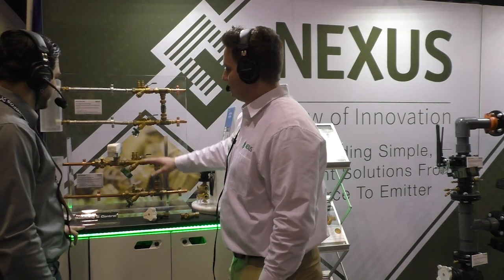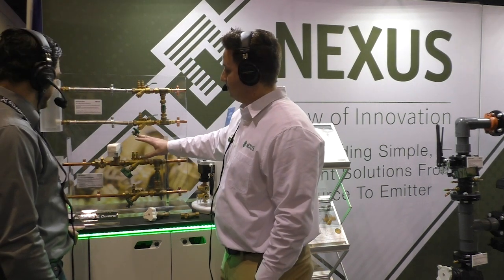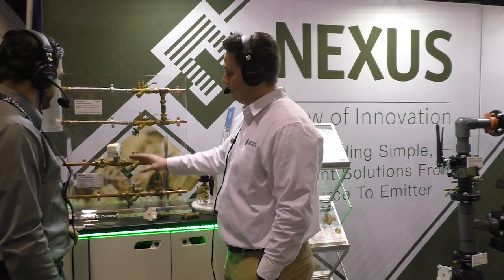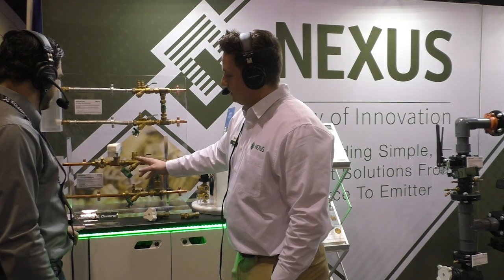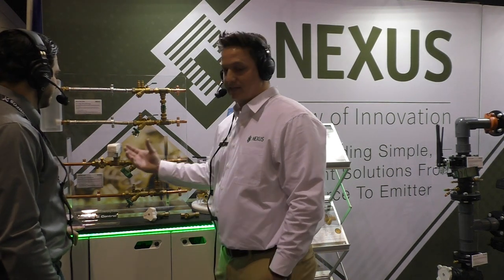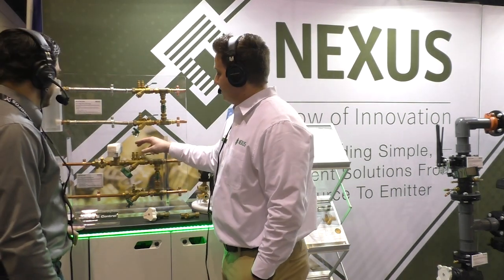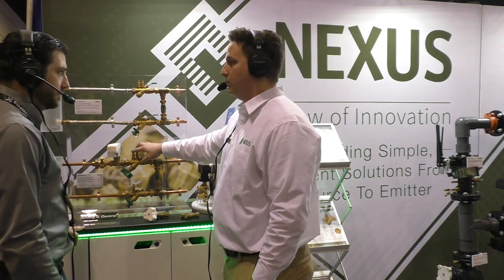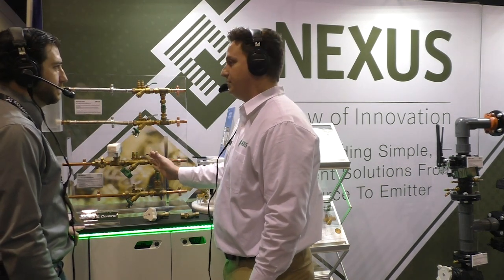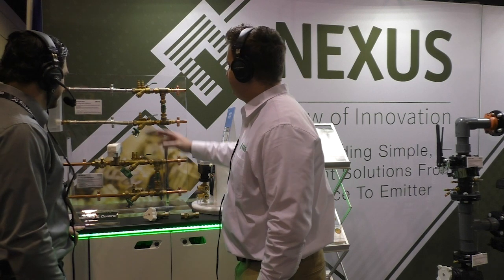In terms of balancing methods, you have the MB, which uses a globe-style balancing valve. You're adjusting the CV inside of that valve, then you can read across the two ports to figure out your differential and get your flow rate.